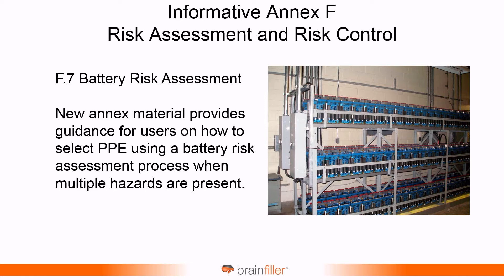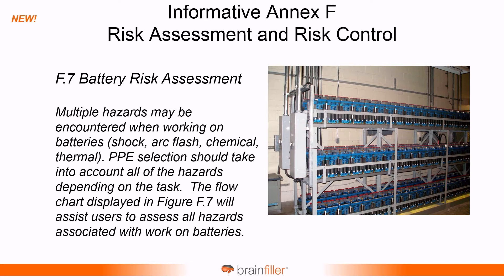There was a new F.7 that was added when you're working around battery systems. F.7 acknowledges that if you're working around battery systems, there's more than one hazard — there are multiple hazards that may be encountered when working on batteries. So you have the shock hazard, the possible arc flash hazard, the chemical hazard, and the thermal hazard. It's acknowledging that PPE selection needs to take into account all these hazards, and there's a flowchart to help with this.